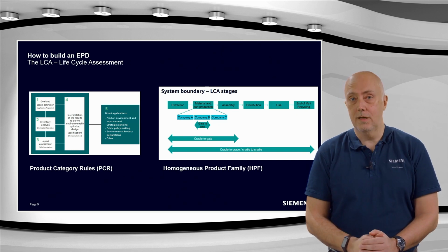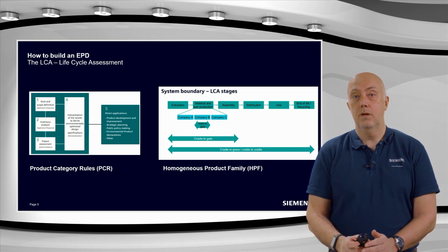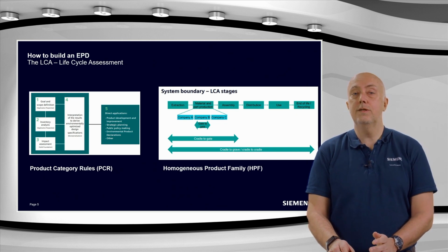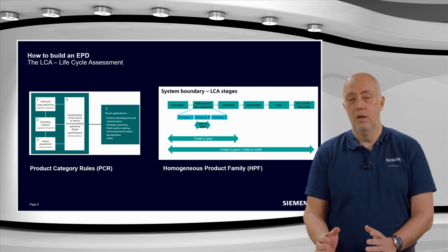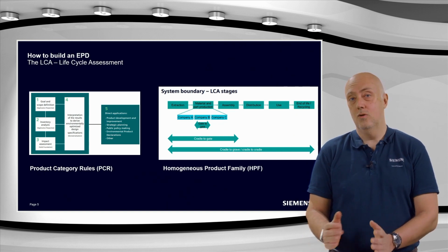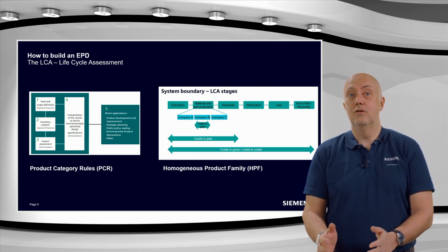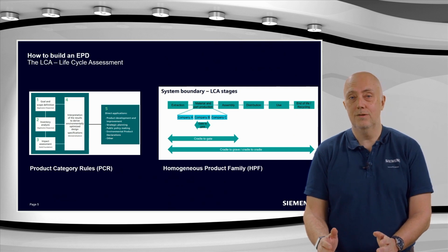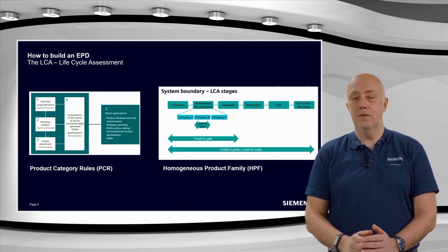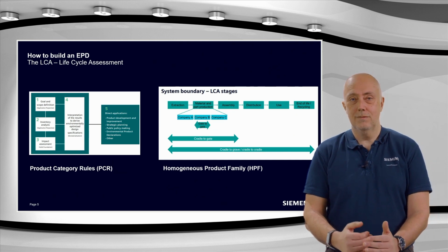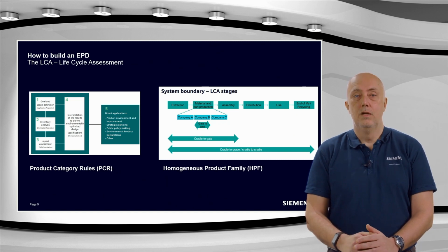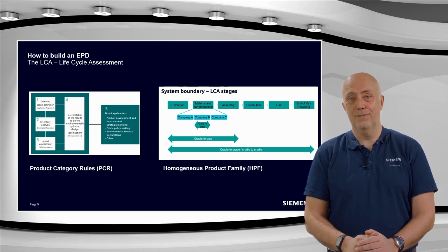One example of non-standardization having an impact on the results of the footprint is the lifetime of the equipment. So our products will have, for instance, resistive losses during the lifetime of the equipment. So we are making assumptions on the load under which the equipment operates, on the source of energy, and on the number of years the equipment will operate to calculate the emissions. So some PCRs will fix a lifetime of 20 years, while others, like the one from Siemens, will use 40 years, doubling the emissions in the second case. So PCRs have a strong impact on the final emissions documented for the product.